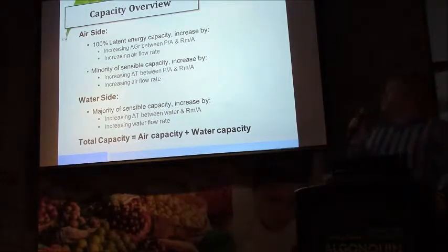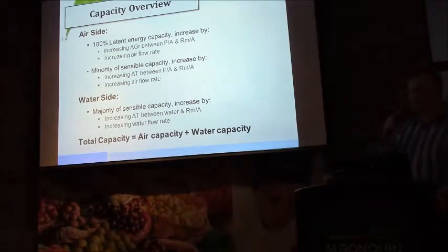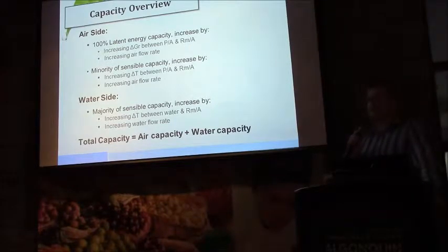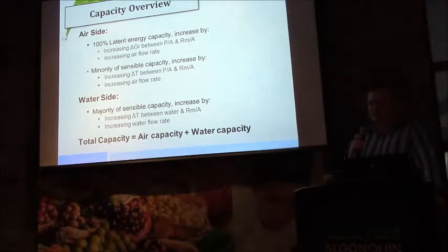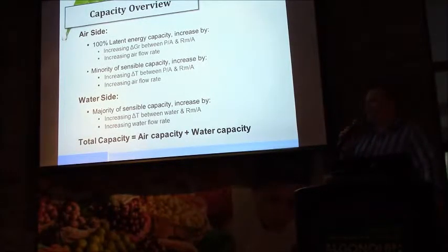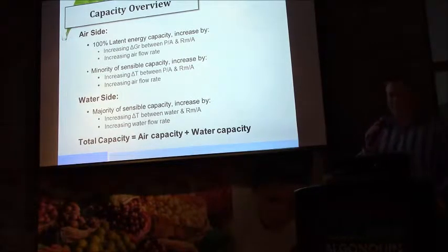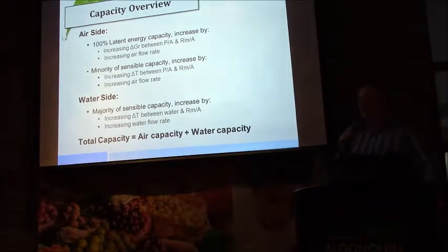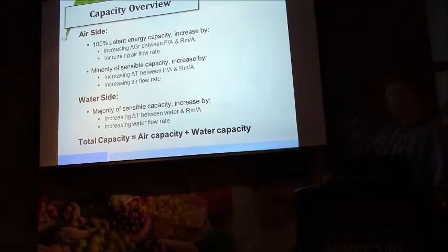So we've dealt with a 100% latent capacity by increasing the grains of separation or the humidity ratio between the primary air and the room design condition, or by increasing the airflow rate. Some of the sensible cooling, of course, will come from that additional primary air. But the water side is also, through Utopia at least, the ultimate opportunity for cooling in the space. The more we can put onto the coil, obviously, the greater the energy return. And the total capacity of the beam is the sum of its parts, being both the air side capacity and the water side capacity of the coil within it.